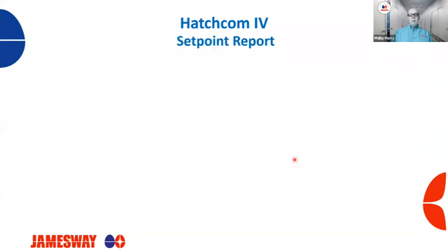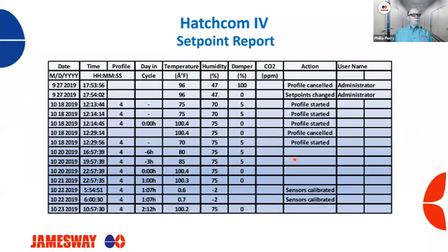The other report that we had was a set point report. What a set point report does, anytime you're running a profile, is show individual changes in the profile. There was no action over here, username or anything. So this machine was just going through profile steps here.